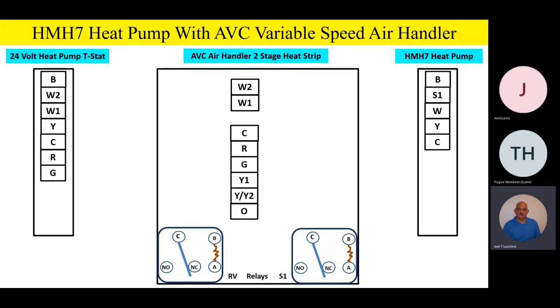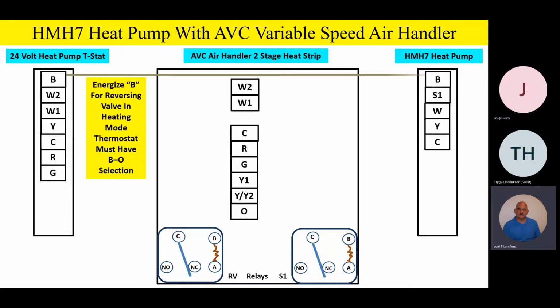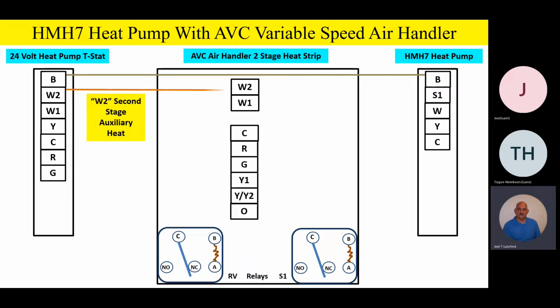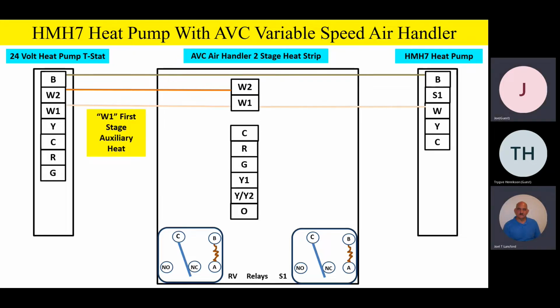You'll notice on the screen we have 2 relays now. We have one relay designated RV relay, and we have another relay designated S1 relay. So just like we had before, it's going to look very, very similar to you. That B terminal is going to go straight outside to the B terminal outside just like we had before. Now, as it turns out, our variable speed air handler and our variable speed furnaces are both two-stage heating capable products. So we're going to feature a W1 and a W2 as well on both products. So on the variable speed air handler, your W2 is going to go to W2 from the thermostat to the indoor product. W1 will be your first stage heating call or your first stage auxiliary heat call. And that's going to be carried straight outside, kind of like we had before, W1 to W1 to W outside.